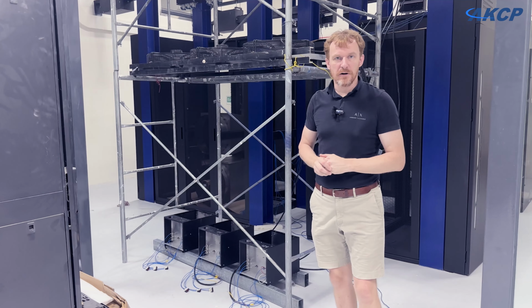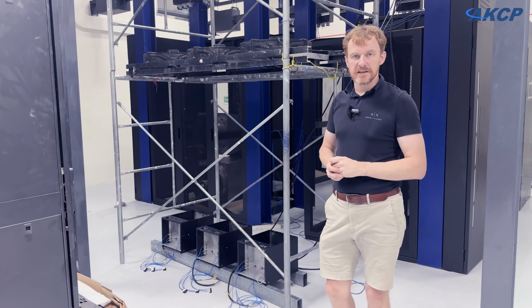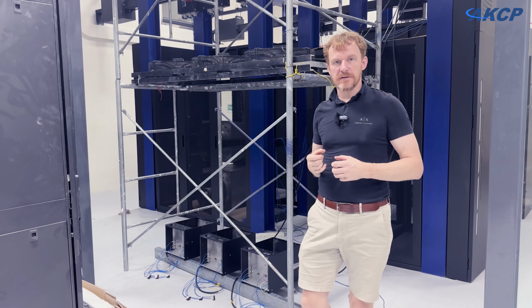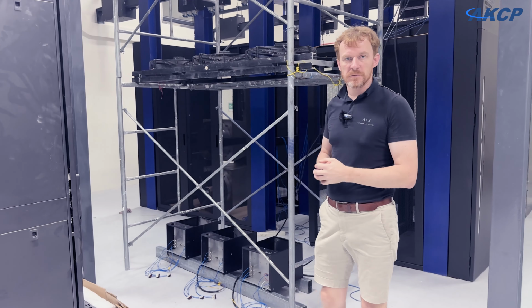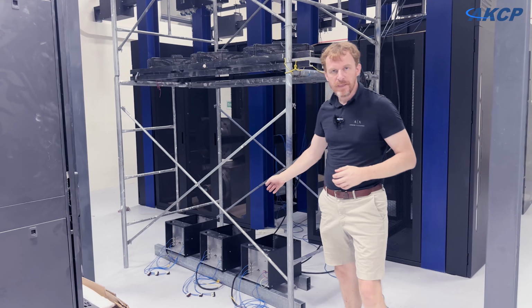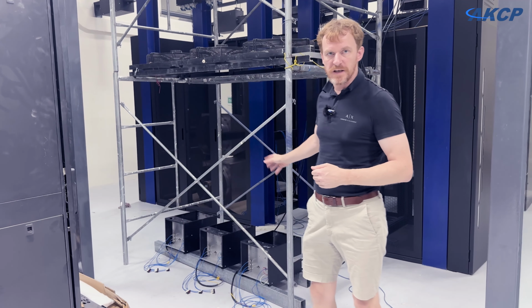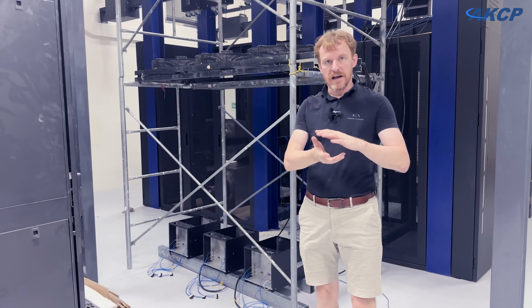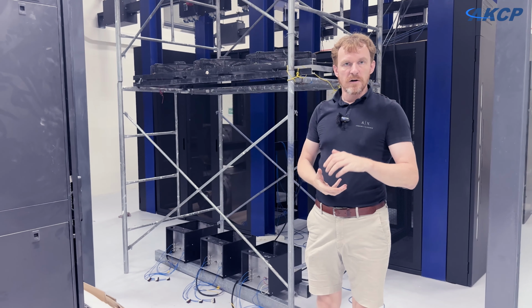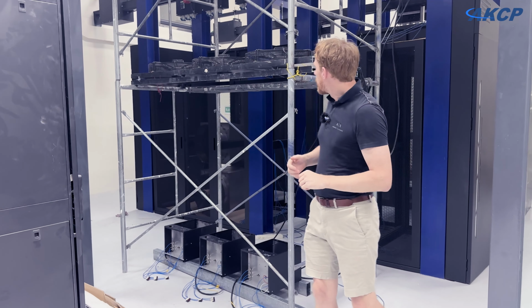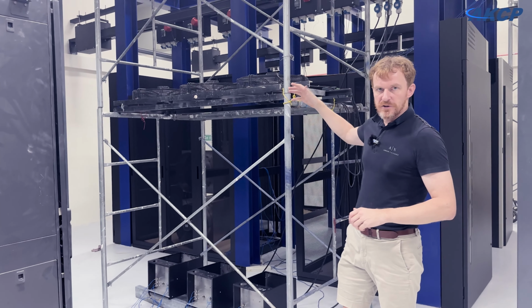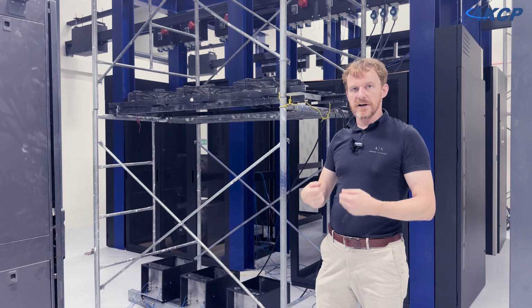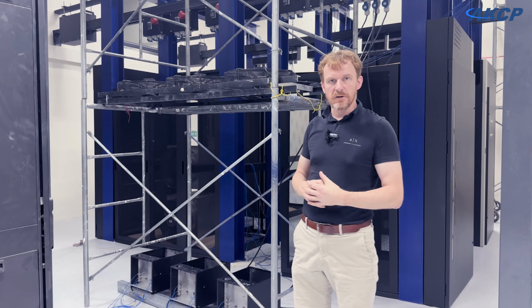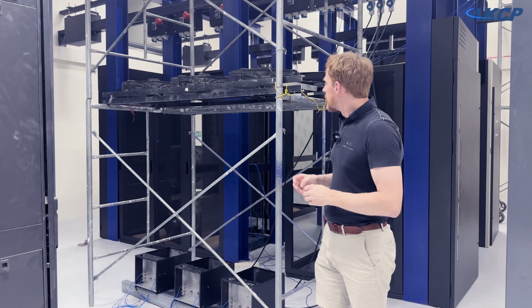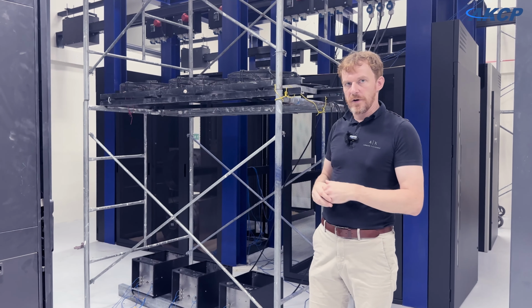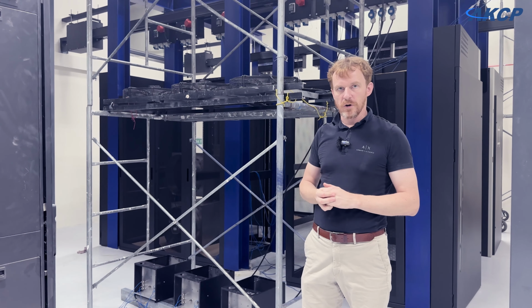We're running a test now. We've got power on our setup for each one of the racks. Rather than filling each one of the racks with actual servers, our heat load is coming from space heaters. What we've got arranged down here is 3 9-kilowatt space heaters. Each one of these will be mounted in the rack. So we have a total of 27 kilowatts potential per rack of heat load that we can generate. Then we've got a series of 3 fans on the front of the rack, which will be pulling the cold air in and cooling off these heaters. So that's how we're going to be generating our heat load in here. 27 kilowatts a rack. In a 10 rack pod, we've got 270 kilowatts in one of the pods.